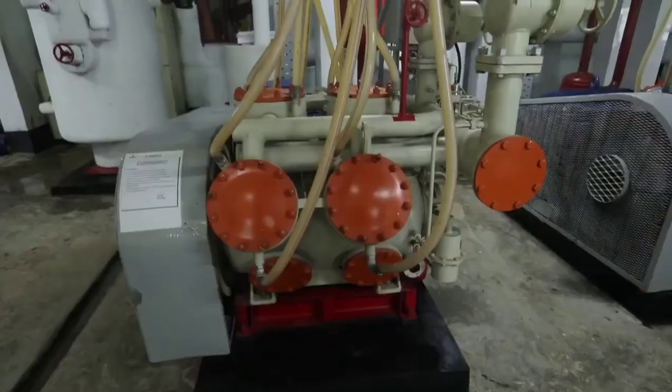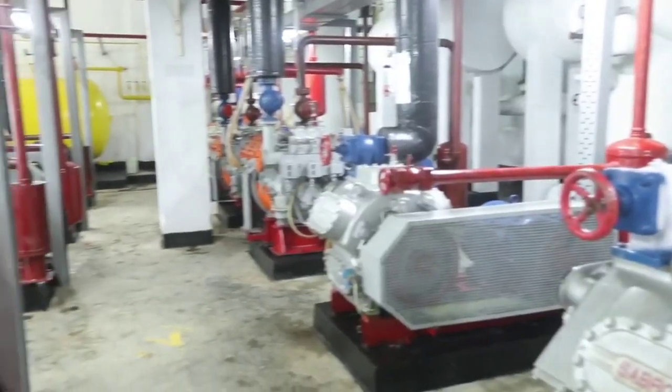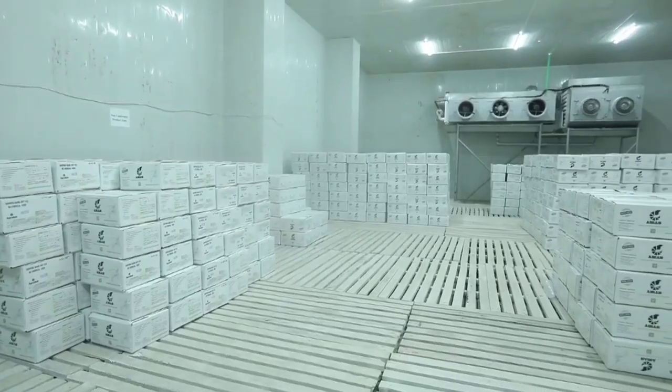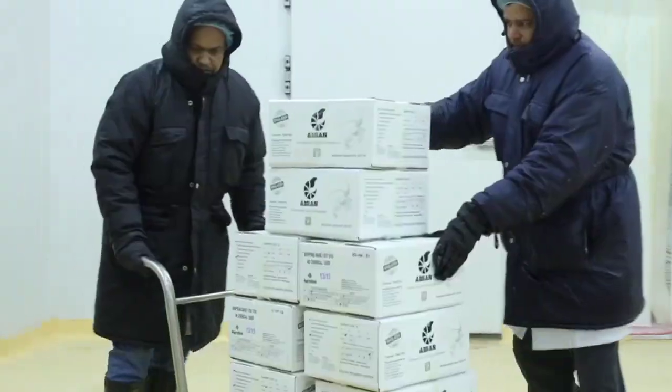Uncontrolled humidity can have big effects on a wide range of operating costs: ice forming on fixtures and equipment, blockage of evaporators, mist forming in the air — all due to slow-opening doors, ineffective defrosting systems, low evaporation temperature, and multiple defrosting cycles creating a heavy load on the refrigeration system. Due to melting and forming ice, barcoding cannot be detected properly and packaging material also gets damaged, creating many disadvantages.